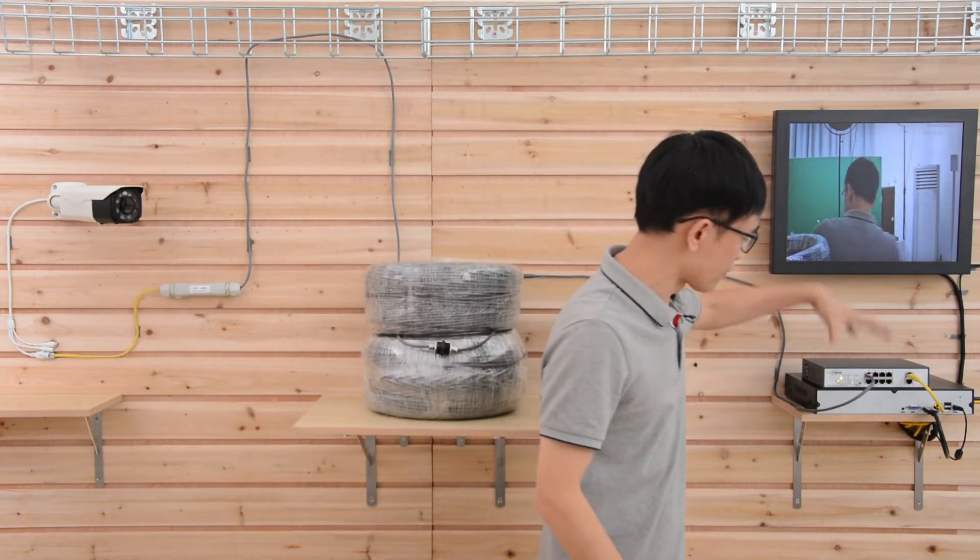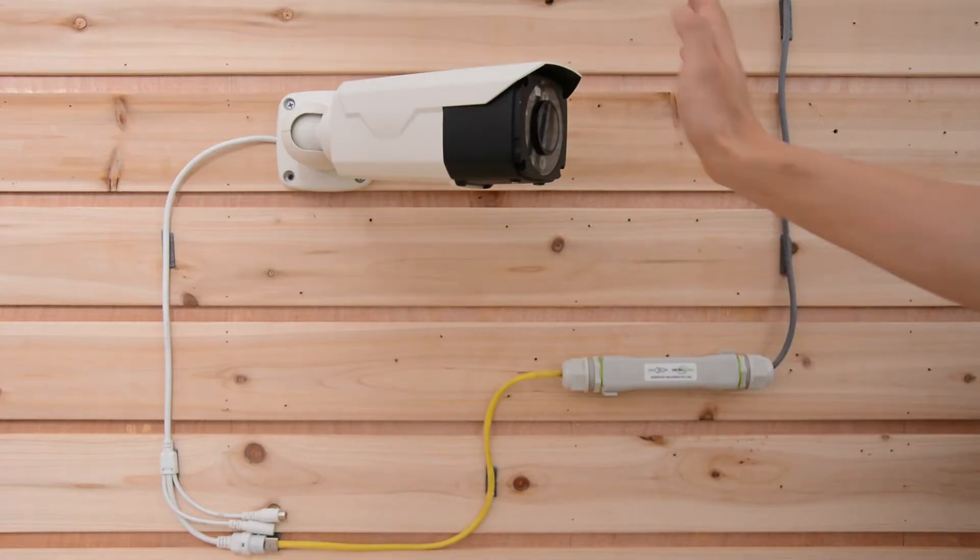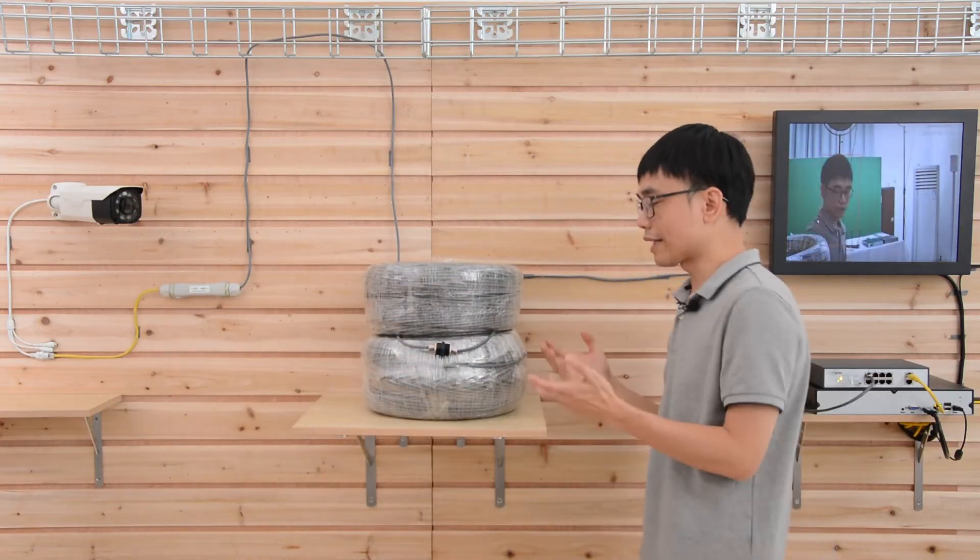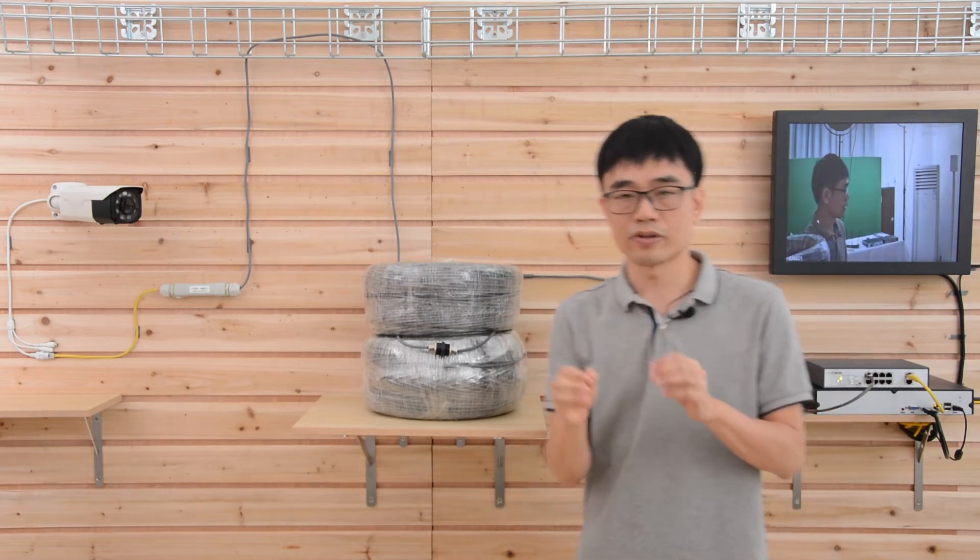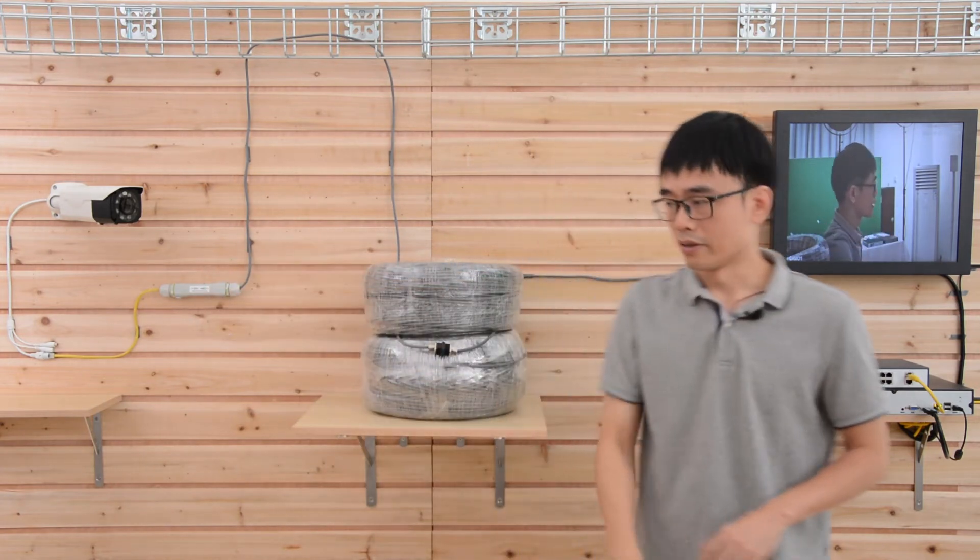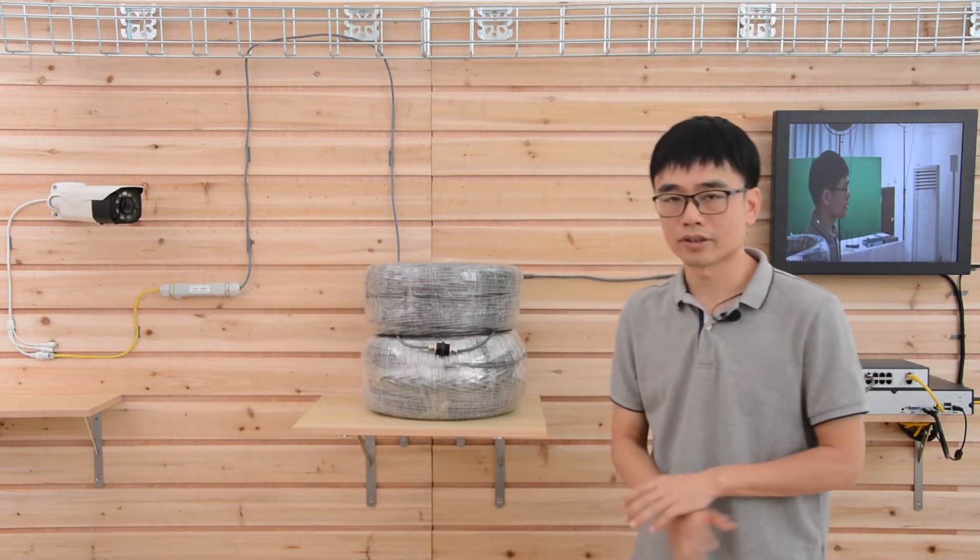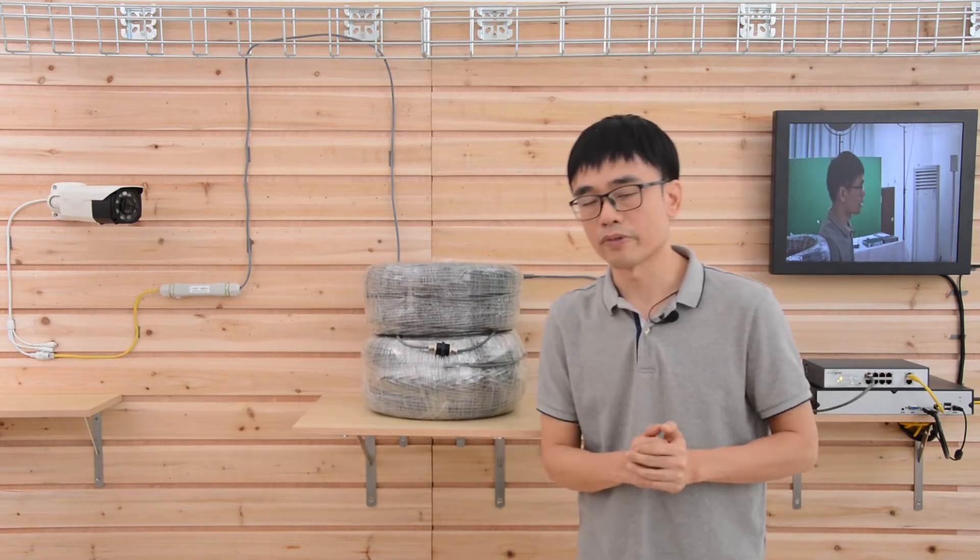So the power is sending from this long run PoE switch and eventually reaches the camera. Now the camera is live. You see, we didn't connect any PoE extender at the middle of this cable. It's just pure continuous run Cat5e from the PoE switch to the camera. There's no need to bury the PoE extender equipment under the ground. We don't need to use the enclosures in the whiteboard we saw.